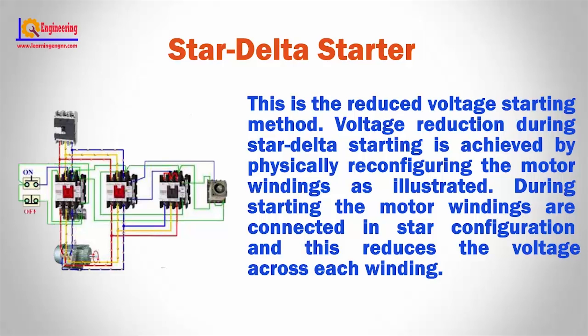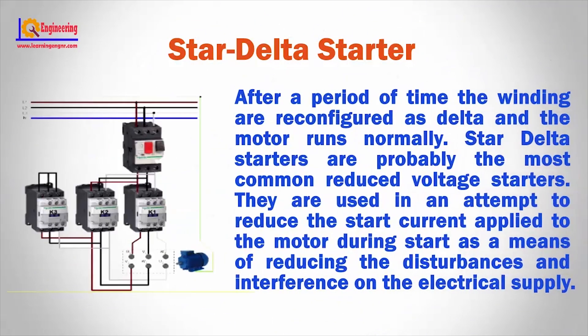During starting, the motor windings are connected in star configuration and this reduces the voltage across each winding. After a period of time, the windings are reconfigured as delta and the motor runs normally. Star delta starters are probably the most common reduced voltage starters. They are used in an attempt to reduce the start current applied to the motor during start, as a means of reducing disturbances and interference on the electrical supply.